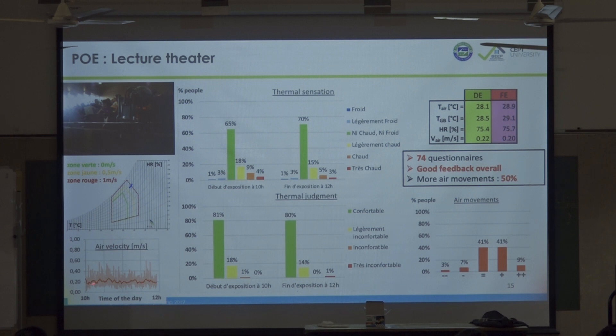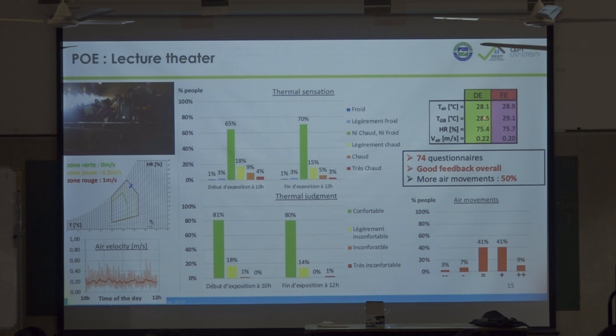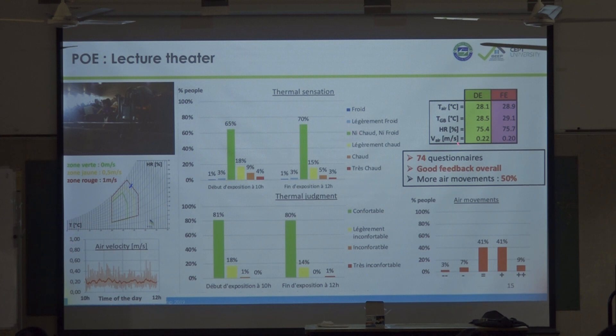We recorded air velocity — the signal is very unsteady but the mean is around 0.2 meters per second — so theoretically users should feel uncomfortable. During this four-hour lecture with 74 people, air temperature was 28 degrees at the beginning and 29 at the end; globe temperature was only 0.4 degrees above, meaning no significant radiant surface. With a velocity of 0.2, normally everyone would say they are very uncomfortable.